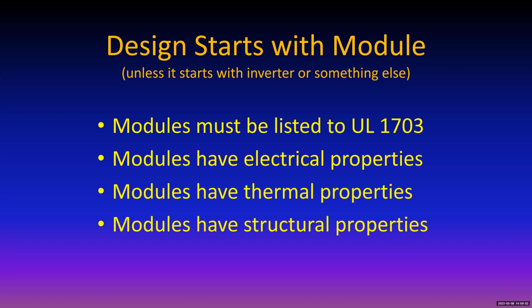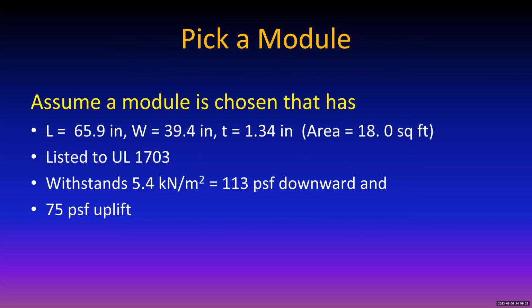And also they are structural. Some are rated at maybe 50 pounds per square foot, and others have ratings up as high as 75, and some are even over 100 pounds per square foot. But you can pay a little bit more for those with the higher ratings because they obviously must have stronger frames. So let's pick one.